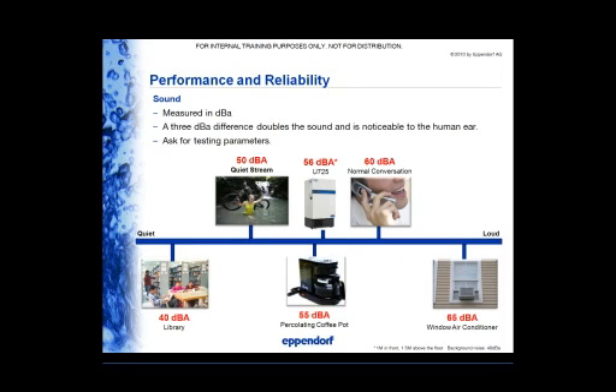Sound. You want to consider sound in terms of performance, and it's an area that is least understood in terms of testing, because, like previously mentioned, there is no standard for testing ultra-low freezers. So sound is one of those ratings that needs to be accompanied not just with a rating, but also the parameters need to be addressed along with the reading. So when you do ask for sound decibel ratings, do ask for the parameters under which it was tested.